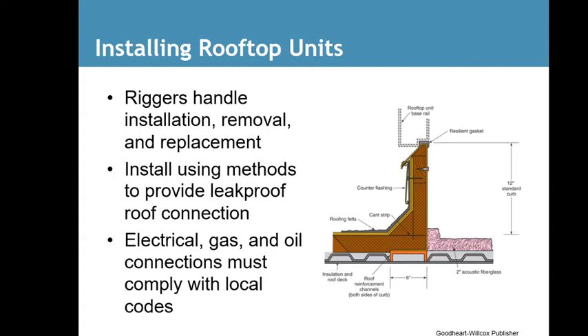Installing rooftop units. Riggers are mainly crane operators. They handle the installation, removal and replacement of the unit. Usually there's a technician there as well, an air conditioning professional, but the riggers handle the movement of the unit while it's being set or removed. Install methods are used to provide leak-proof roof connections, and there's a diagram of what one should look like. Gas, electric and oil connections must comply with local codes. Remember, the gas, electric, and water drains are going to have to go through the roof of the building to get to wherever they need to go. So those things have to be sealed up and have to meet code.